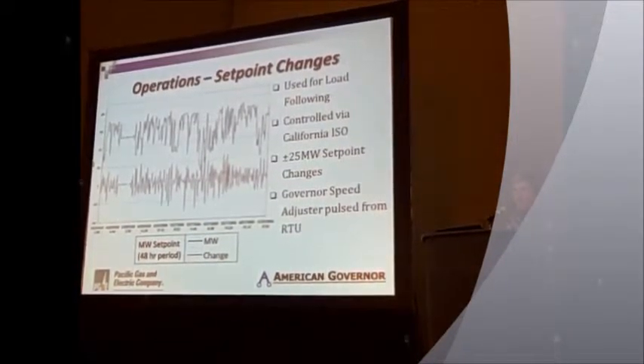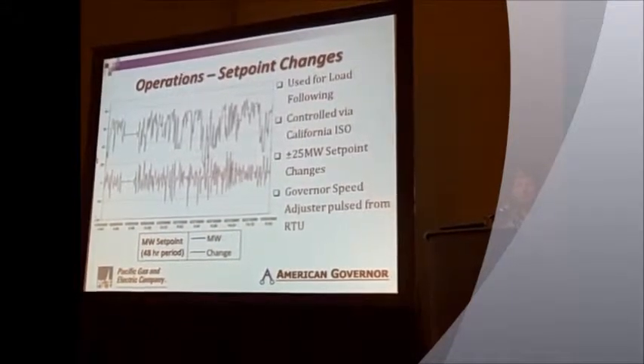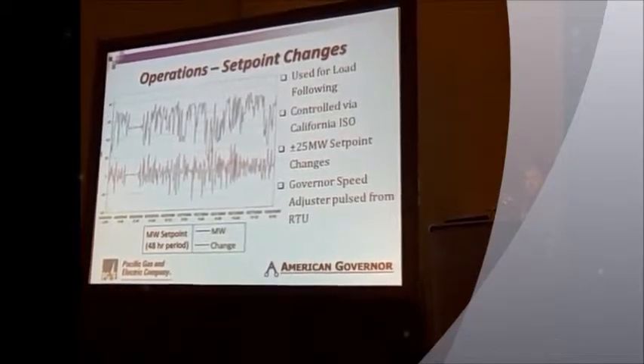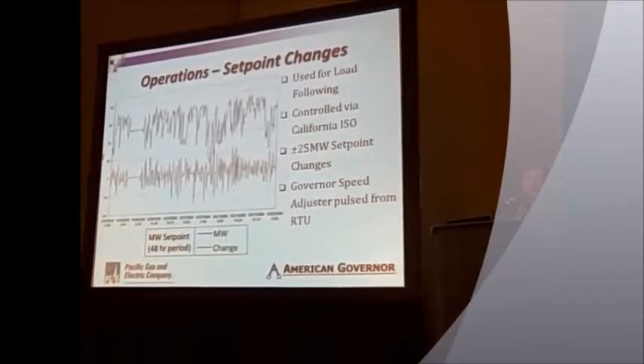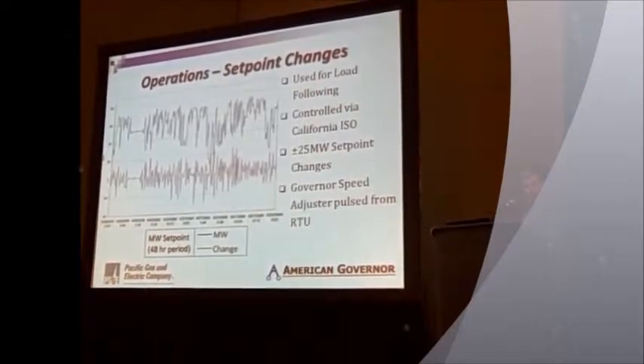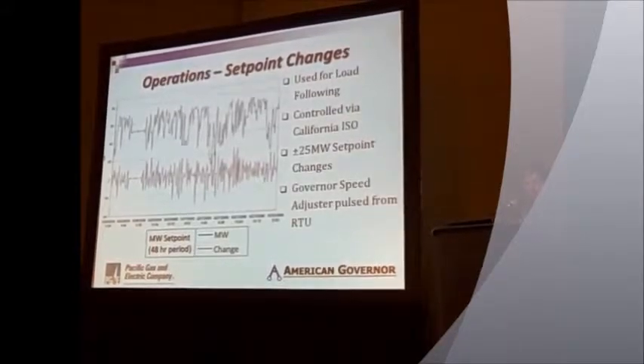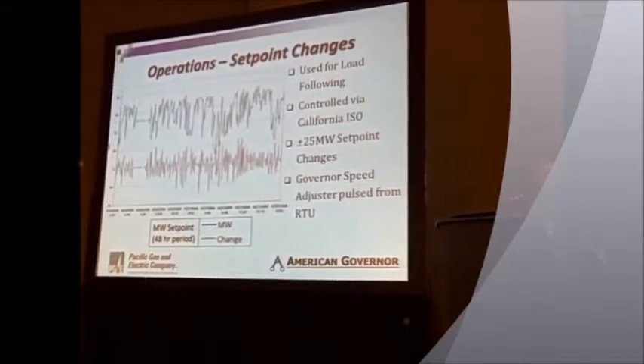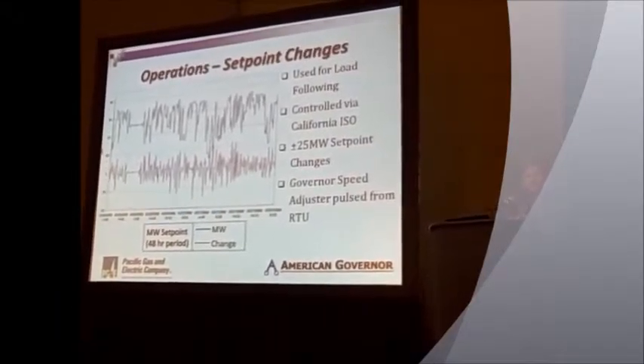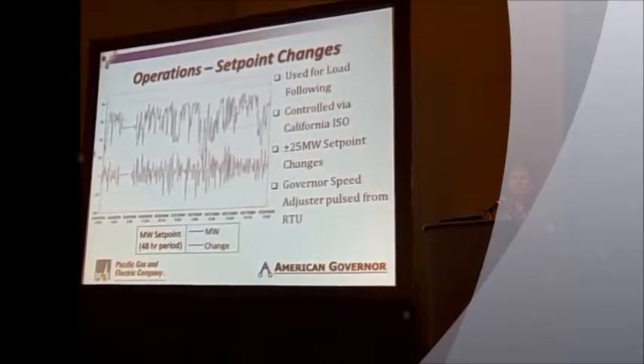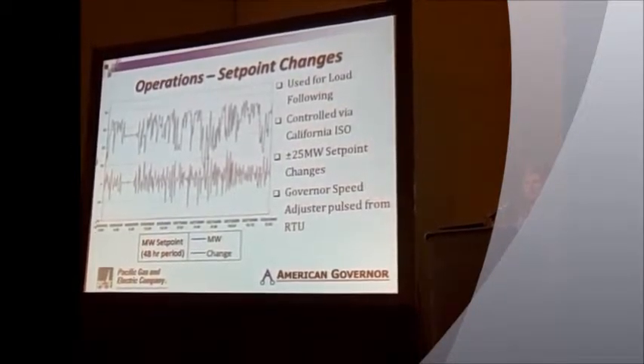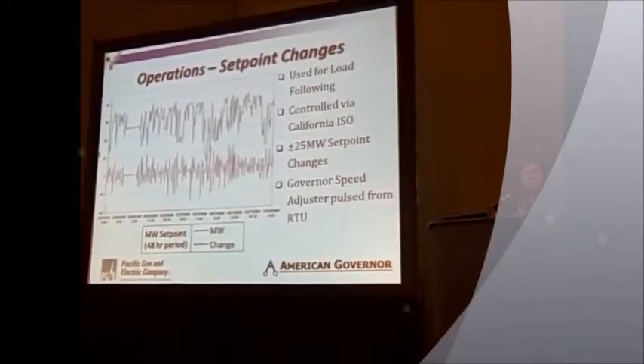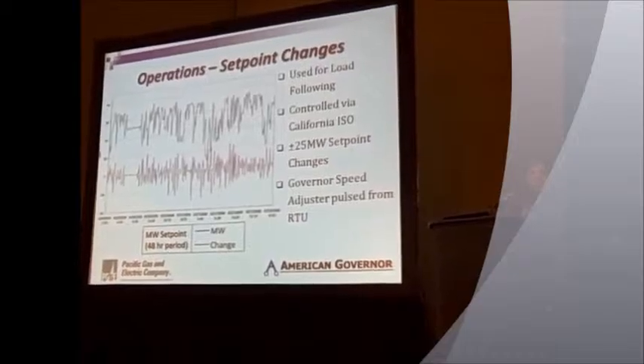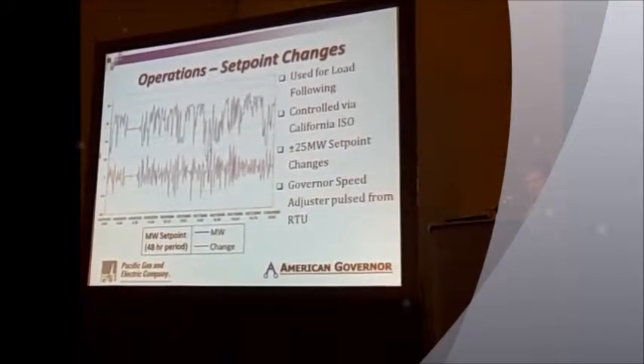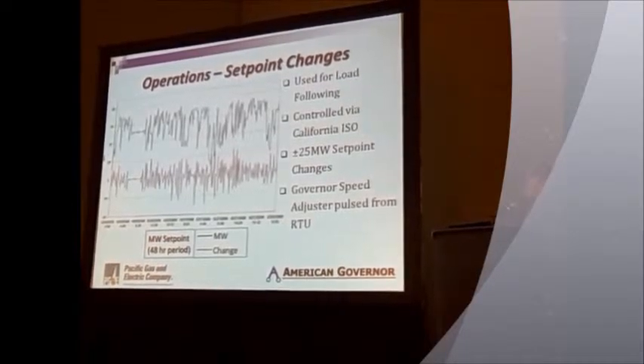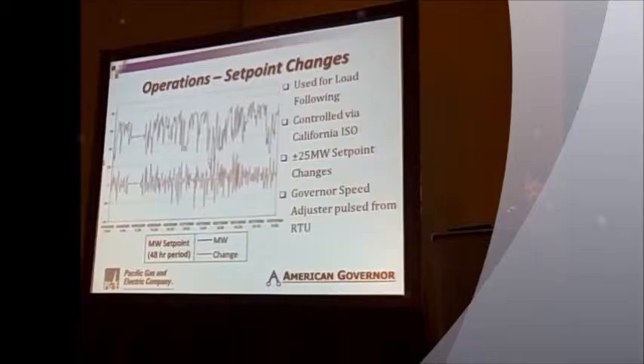As I mentioned, one of the major issues in this plant was that it's used for ISO load following. They would make easily over 100 megawatt set point changes in a day, and they could be as much as 30 to 40, 50 megawatts at a time. The ISO would send an analog set point to our control center. That would turn around and send digital pulses to the RTU at the powerhouse. That in turn operated the interposing relays and then operated the speed adjust motor. So the speed adjust motor was in constant flux, just being bumped up and down. As a result, the speed adjust motors lasted about 18 months and usually failed about 2 weeks before our scheduled outage, so I had to deal with a forced outage just in time.